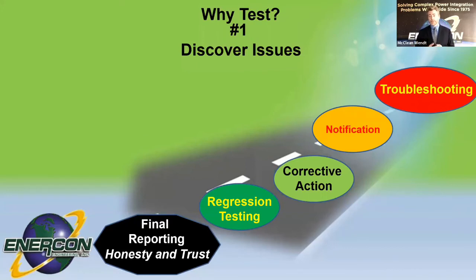Once you've troubleshot the issue and found out what the issue is, you do the corrective action. Oftentimes, depending on what it is, if it's small, then we can fix it or send it back to production to have them fix it. And then the next part would be once the corrective action is approved and implemented, I need to figure out what kind of regression testing needs to be done. Does any of the repair disqualify or invalidate the results from previous testing? Or can you just continue on from where you were at?